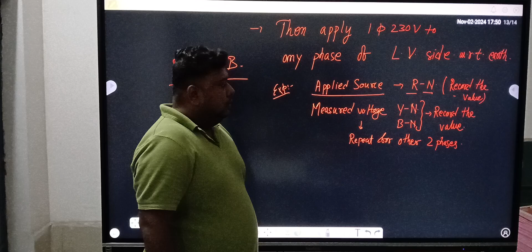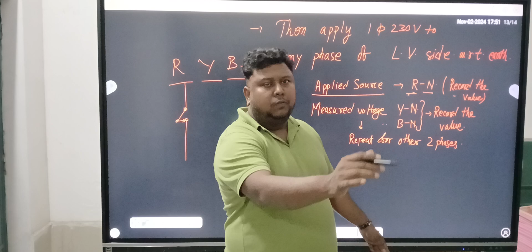After recording the value, again we have to measure the voltage of the other two phases. I have given the supply to R, so what are the phases left out? Y and B. So for Y and B with respect to neutral, I have to measure the voltage. Neutral means we touch any part of the body of the transformer; that will be our neutral. So I measure the voltage of Y to neutral and B to neutral, and record the values. There are also some practical values already recorded; I will show you.